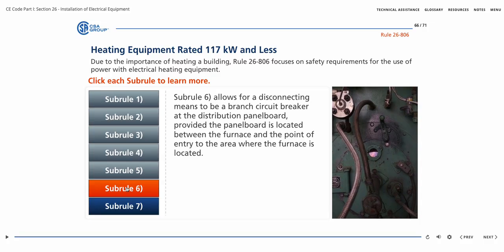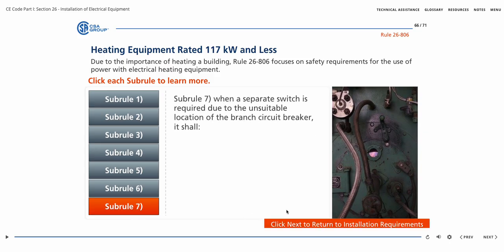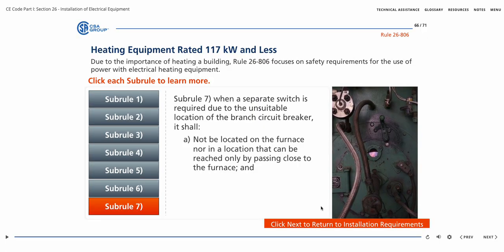Sub-Rule 6 allows for a disconnecting means to be a branch circuit breaker at the distribution panel board, providing the panel board is located between the furnace and the point of entry to the area where the furnace is located. In Sub-Rule 7, when a separate switch is required due to the unsuitable location of the branch circuit breaker, it shall A. Not be located on the furnace, nor in a location that can be reached only by passing close to the furnace, and B. Be marked to indicate the equipment it controls.